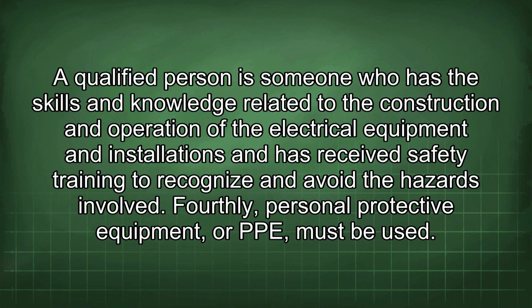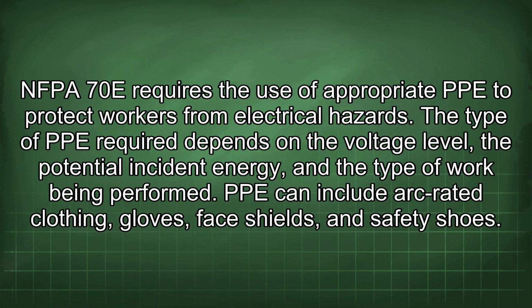Fourthly, personal protective equipment, or PPE, must be used. NFPA 70E requires the use of appropriate PPE to protect workers from electrical hazards. The type of PPE required depends on the voltage level, the potential incident energy, and the type of work being performed. PPE can include arc-rated clothing, gloves, face shields, and safety shoes.